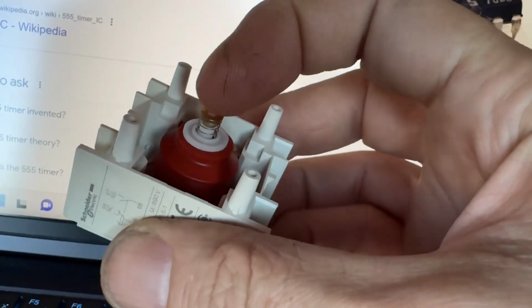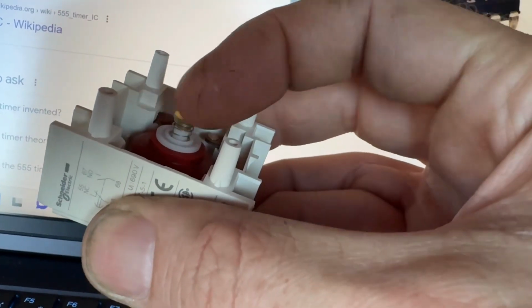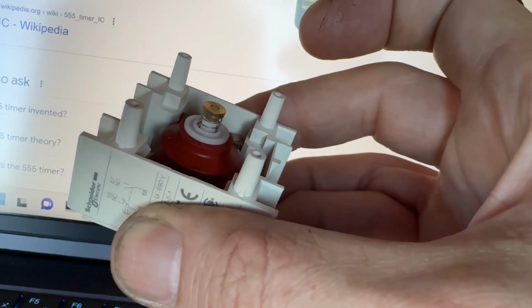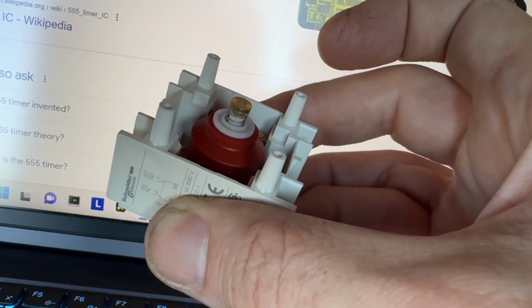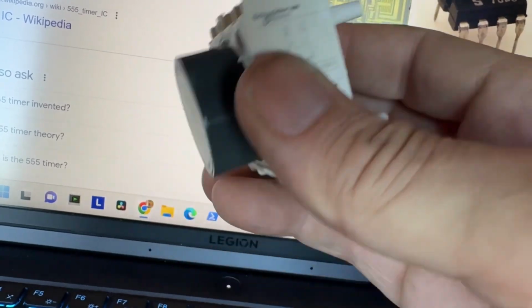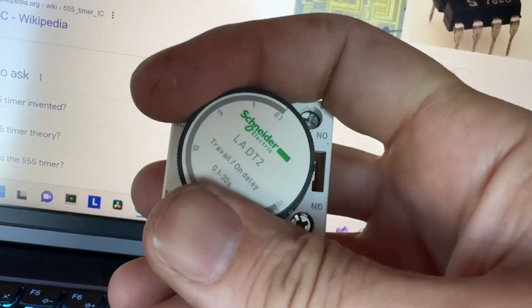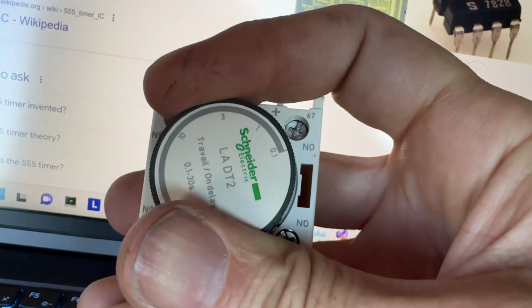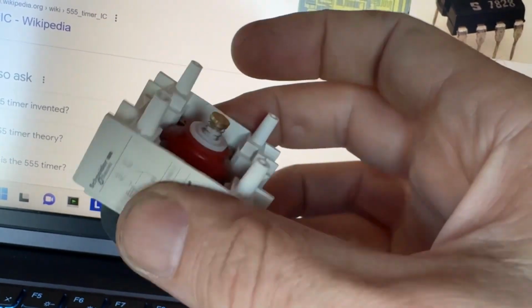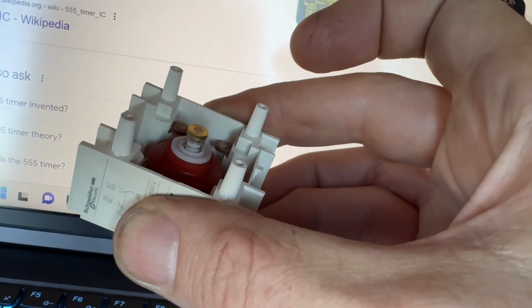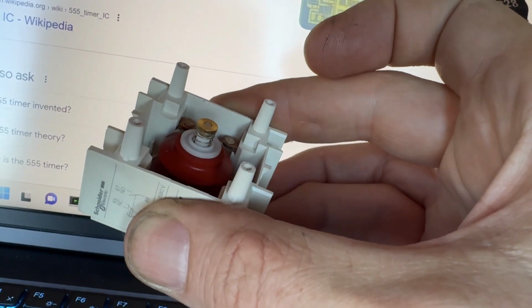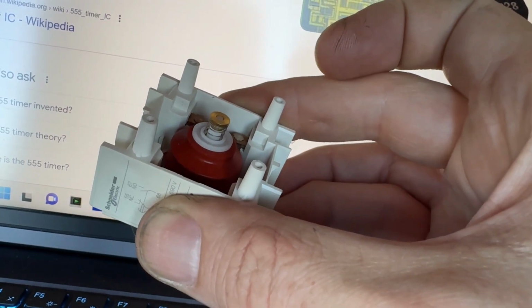Now if I push this down, that little thing will slowly rise up, and it takes about a second to fully rise up. So that is your 1 second delay. If I dial this up to say 3 seconds, and push it again, it now rises up much slower. In fact, it takes 3 seconds to rise up.